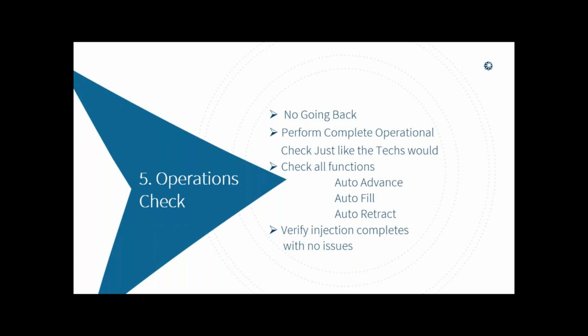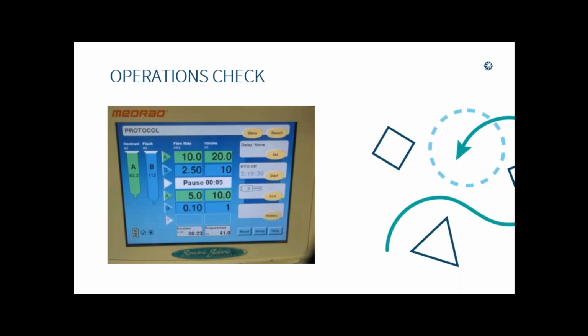Check all functions: auto advance, auto fill, auto retract. Verify injection completes without any issues. You're going to do that at the end also, before you hand it back to the customer. There's the protocol right there that Bayer puts in for us. It's in the manual, and actually the technician is supposed to be doing this too on a daily basis.